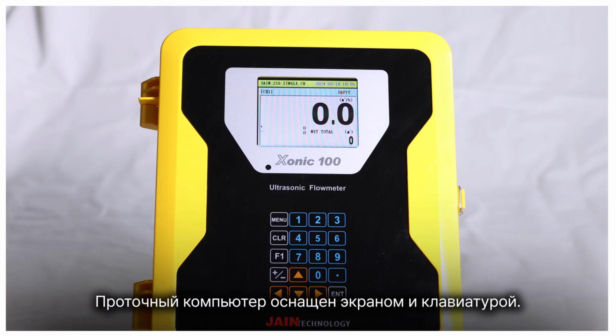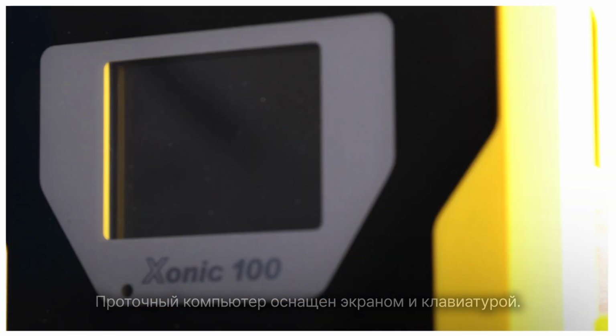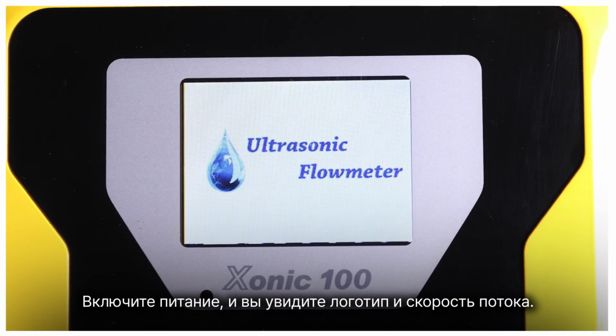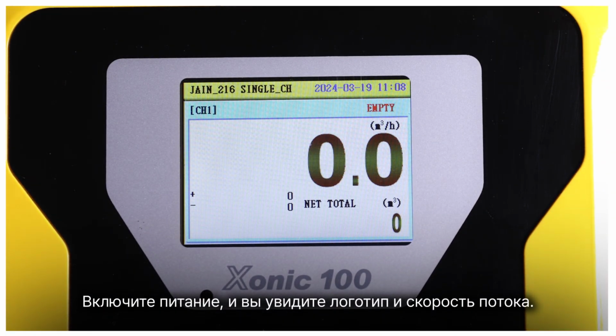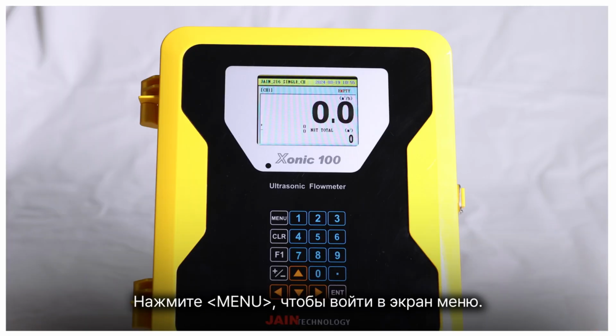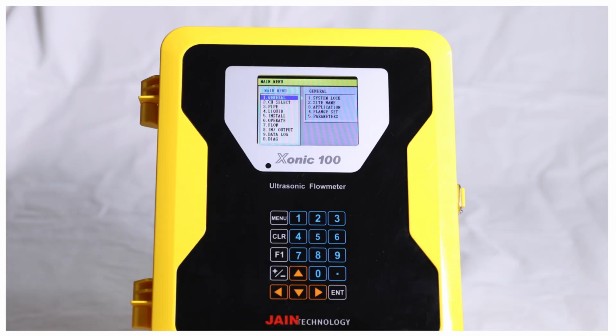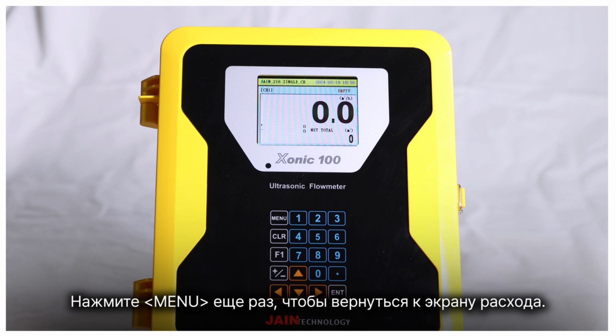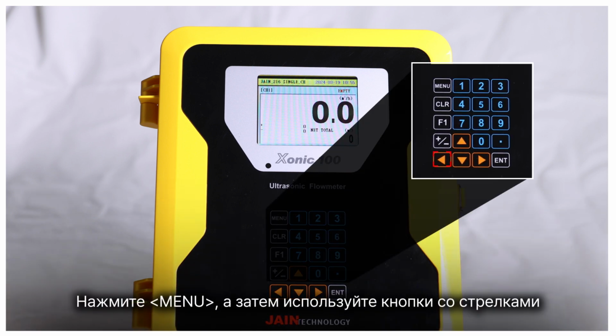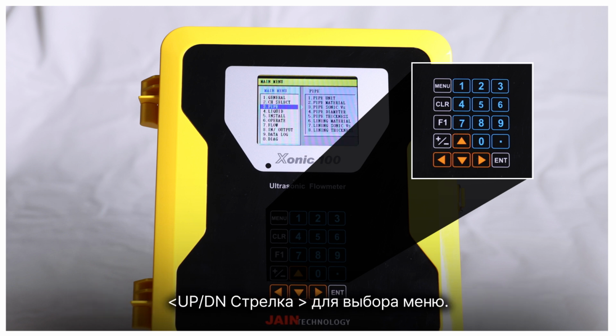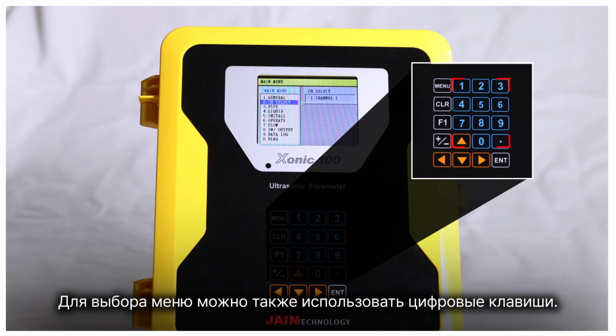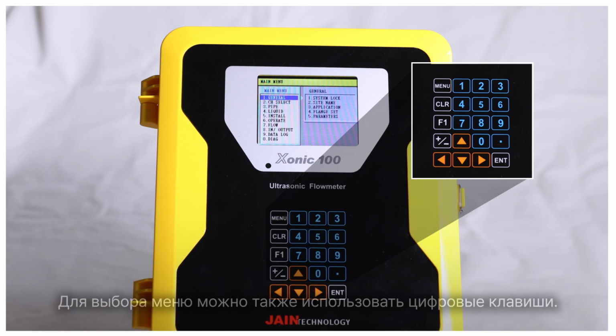The flow computer has the screen and a keypad. Turn on the power and you'll see the logo and flow rate. Press Menu to enter the menu screen. Press Menu again and it switches back to the flow screen. Press Menu and then use the up and down arrow keys to select a menu. You can use the number keys instead to select a menu as well.